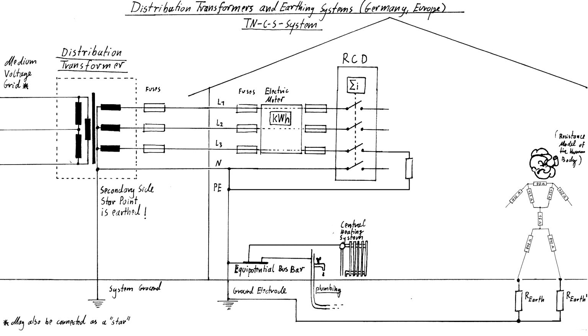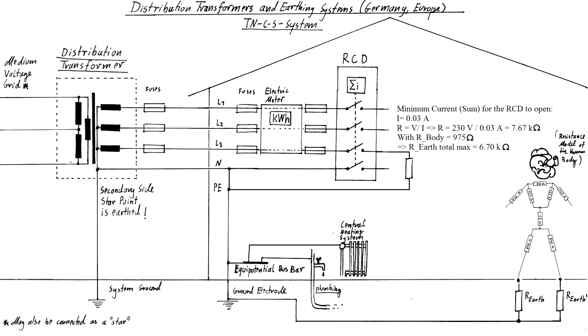Nowadays, these RCDs are normally rated for 30 milliamperes. With that figure and the supply voltage of 230 volts, you can calculate that the resistance required to activate the RCD is around 7.6 kiloohms. For a person standing on the ground, that would be the sum of their body resistance plus the total resistance of the earth return path to the ground electrode or to the system ground respectively.